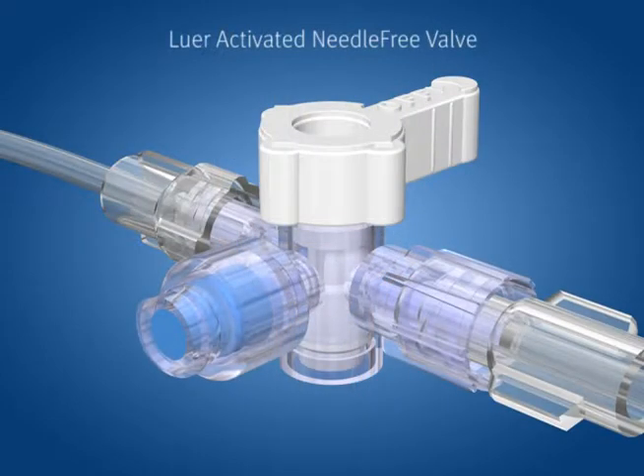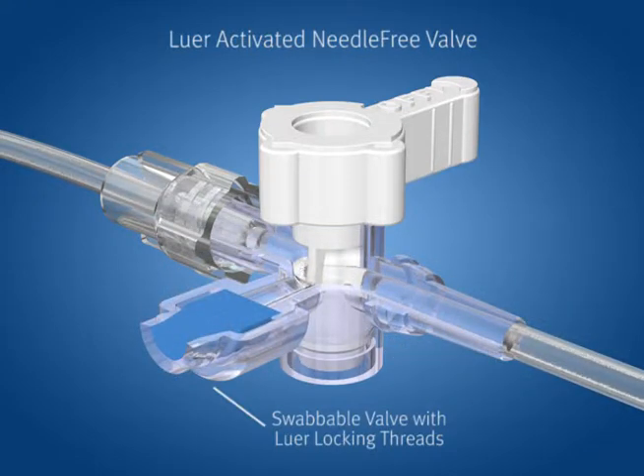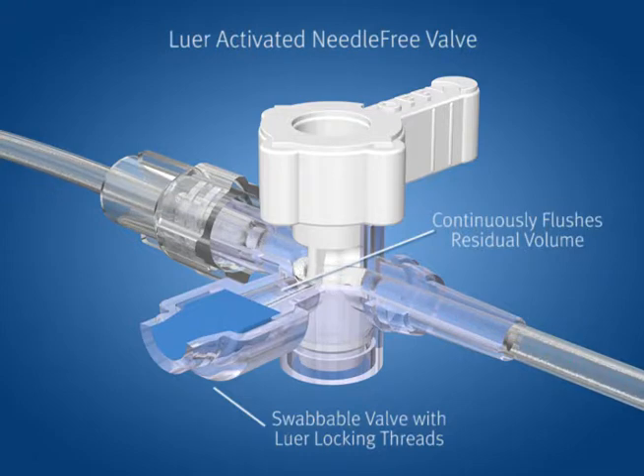Complete needle-free access to the patient's blood is provided through the use of the novel swabbable valve. This valve utilizes key design features that eliminate some of the additional steps required during the priming and flushing process when using the traditional swabbable valve for blood sampling.